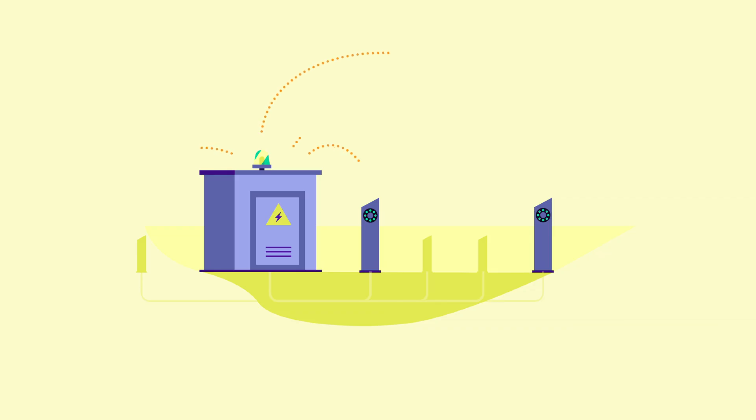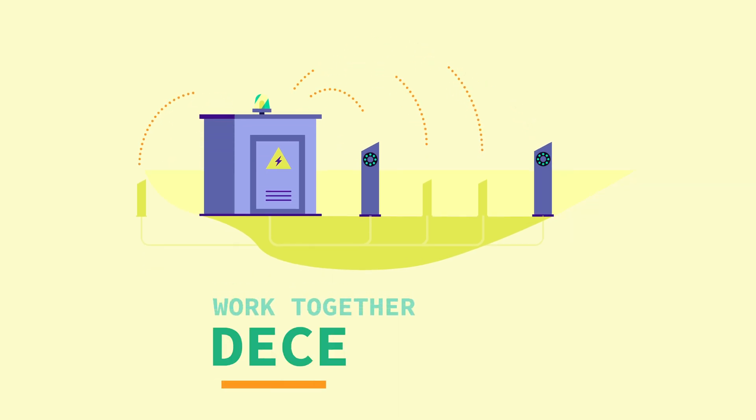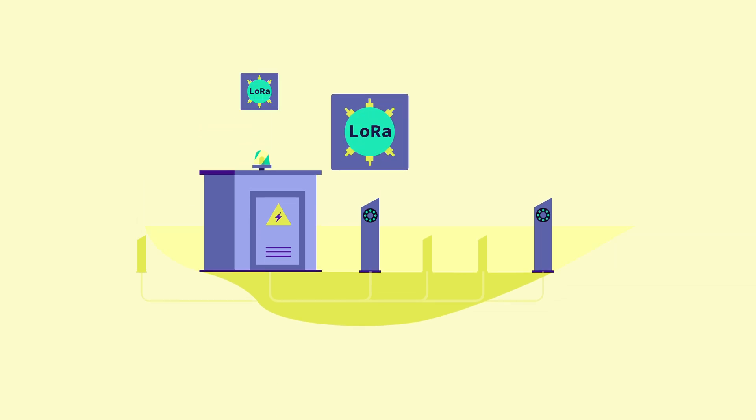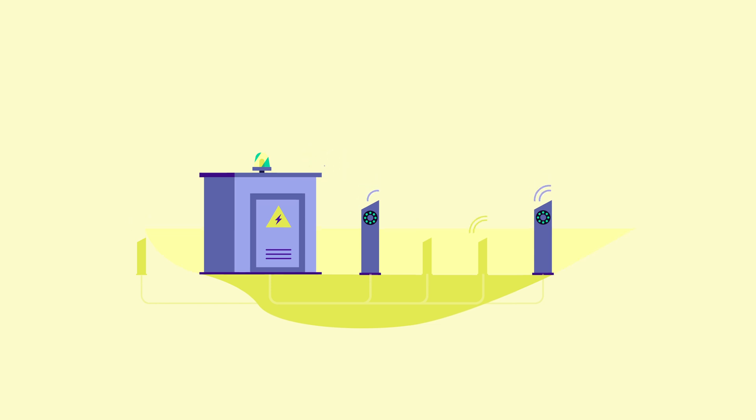In the other solution, a group of charging stations work together decentrally, without being dependent on a central platform. This is run by the so-called LoRa network. A signal is sent from the transformer to the neighbourhood charging stations, telling them to charge at a lower rate.